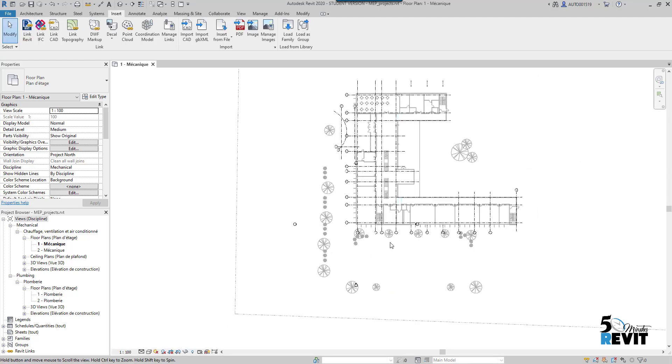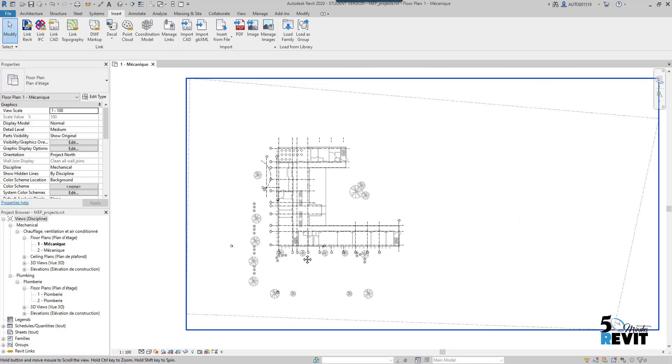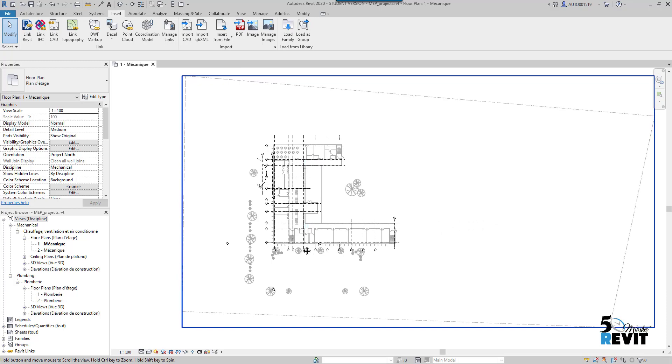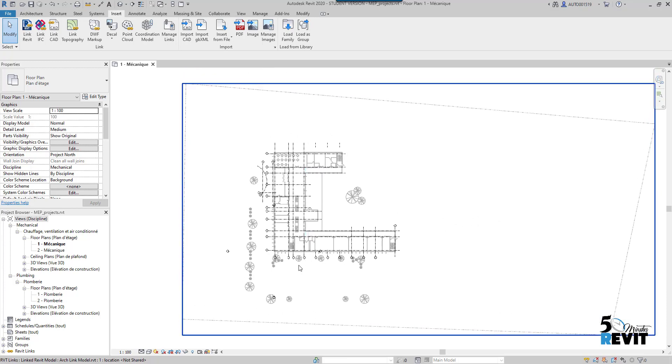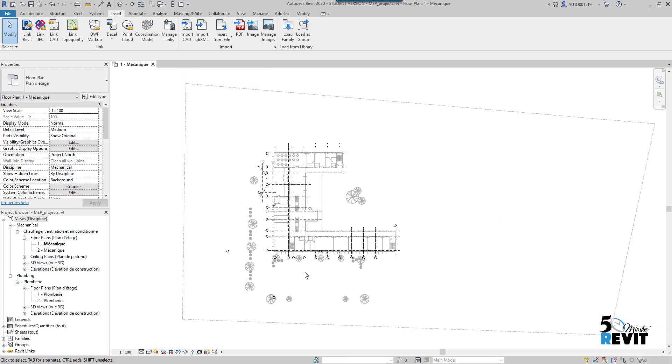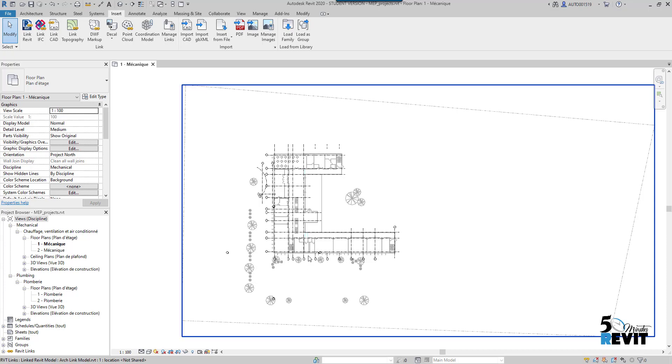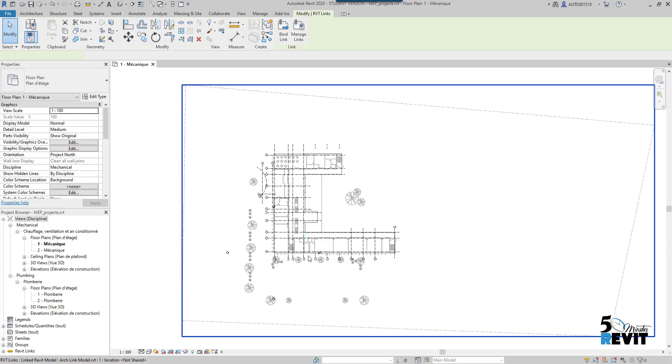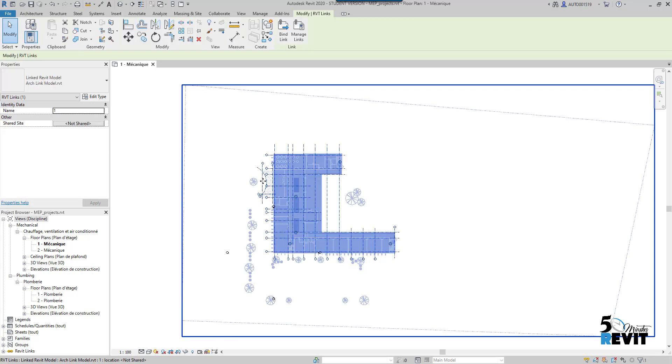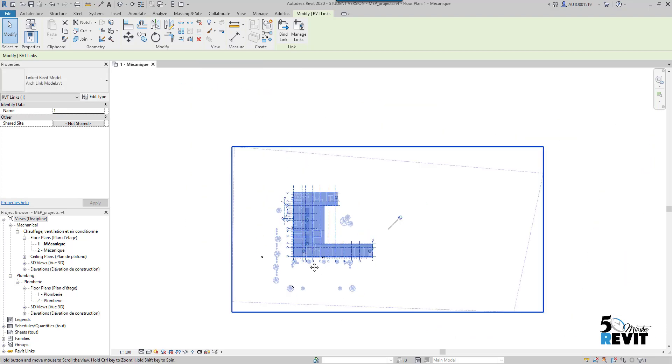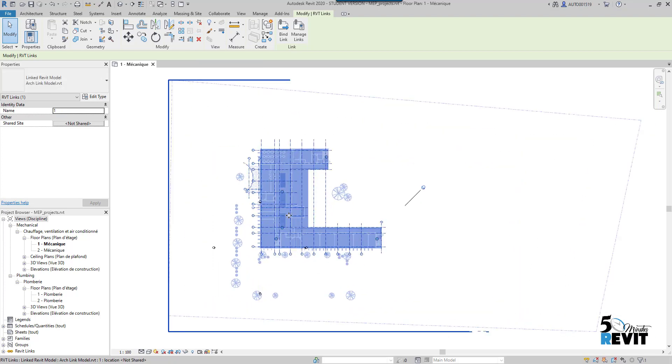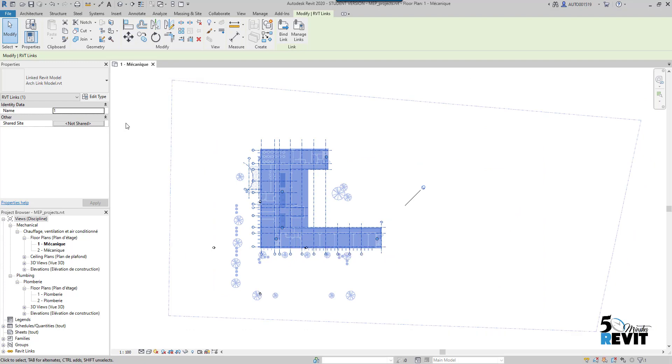Now I have my architecture file linked to my MEP model, my mechanical model in this case. I select the link and I pin it. It's the first thing you do - pin it so it doesn't move. Second thing, you select your link, go to Edit Type, and check Room Bounding. I will explain why. Just apply and put OK.